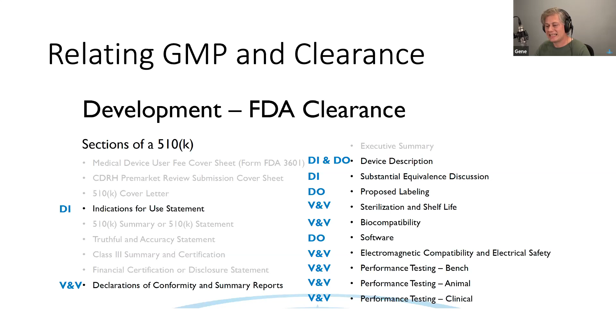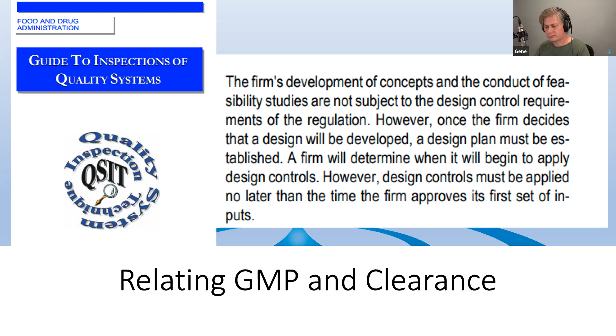But is it always applicable? Well, here's an answer to that. And this is from the Quality System Inspection Technique Guide by FDA to their quality system inspectors. And they note that the firm's development of concepts and the conduct of feasibility studies are not subject to the design control requirements of this regulation. However, once the firm decides that a design will be developed, a design plan must be established. A firm will determine when it will begin to apply design controls. However, design controls must be applied no later than the time the firm approves its first set of inputs. So this link between those two worlds finds its start when the firm approves its first set of design inputs. And from there, you need to start thinking about design controls. And from there, you need to build your management systems. From there, you need to build your manufacturing procedures, hopefully with the help of a great manufacturing partner.